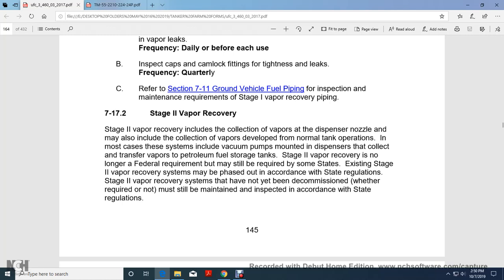Alright, 7-17.2, Stage 2 Vapor Recovery. Stage 2 Vapor Recovery includes a collection of vapor at the dispenser nozzle, and may also include the collection of vapor depending on the normal tank operation. In most cases, the system uses vacuum pumps in the dispenser that collect and transfer the vapor to the petroleum fuel storage tanks. Stage 2 Vapor Recovery is no longer a federal requirement, but is still required by some states.